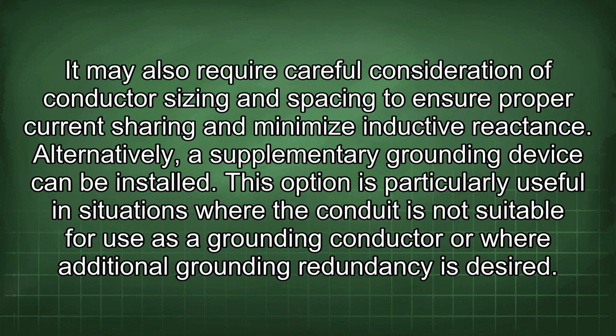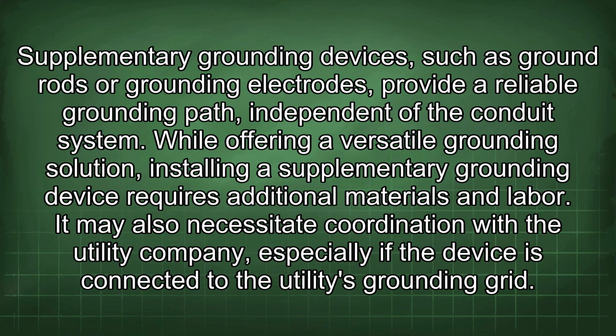Alternatively, a supplementary grounding device can be installed. This option is particularly useful in situations where the conduit is not suitable for use as a grounding conductor or where additional grounding redundancy is desired. Supplementary grounding devices, such as ground rods or grounding electrodes, provide a reliable grounding path independent of the conduit system. While offering a versatile grounding solution, installing a supplementary grounding device requires additional materials and labor. It may also necessitate coordination with the utility company, especially if the device is connected to the utility's grounding grid.